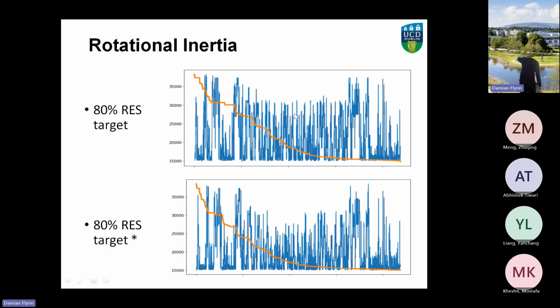What I'm plotting here is rotational inertia in megawatt seconds, with time on the horizontal axis. The blue curve represents time measured across the year, and the orange curve is everything ranked by inertia value. At the minute, the minimum inertia on the Irish system has to be at least 23,000 megawatt seconds. In the future that will reduce, potentially to a minimum of maybe 15,000 megawatt seconds, because we're displacing conventional generation and operating with more variable renewables.